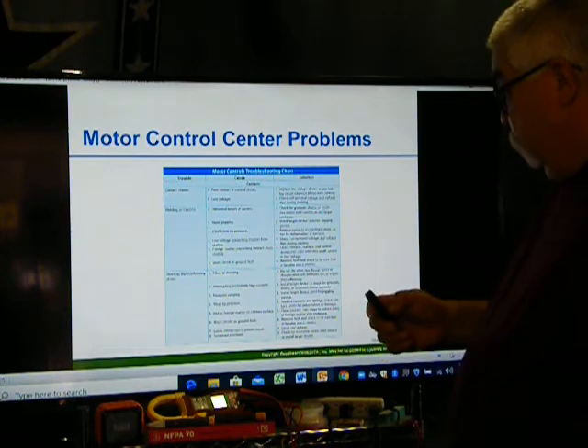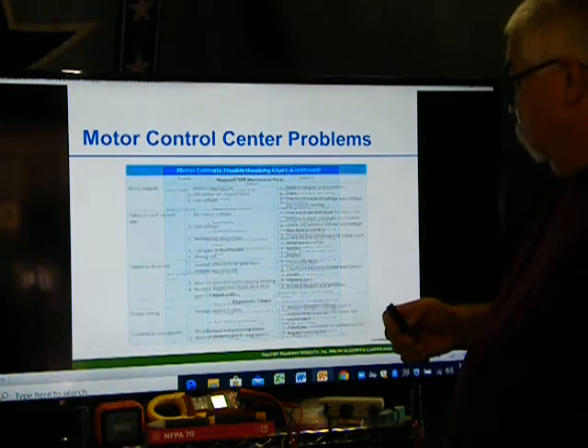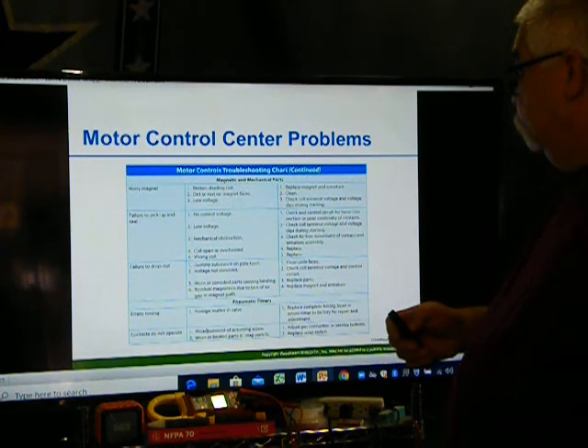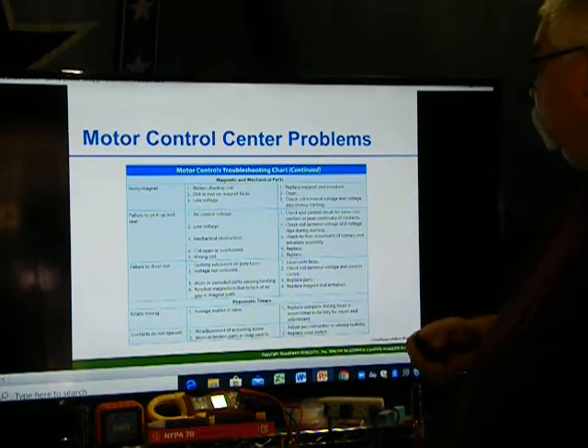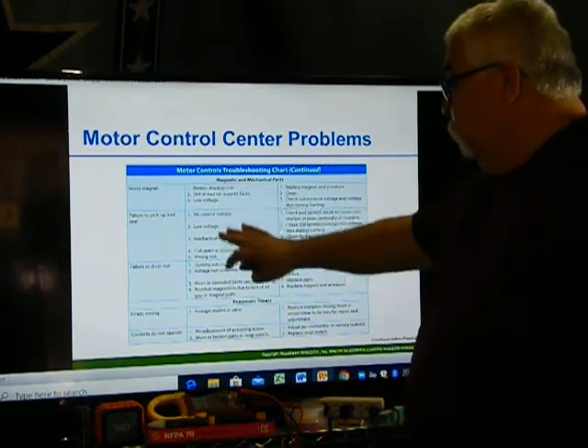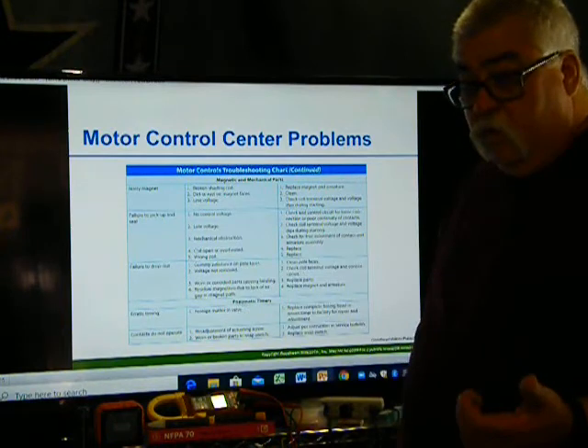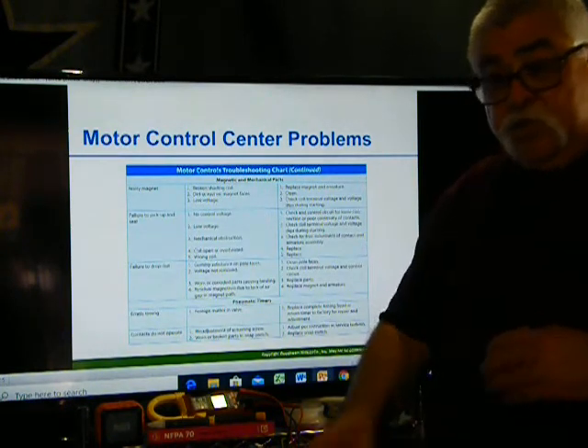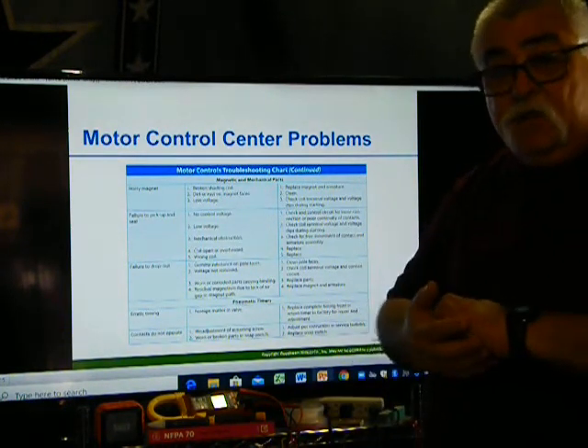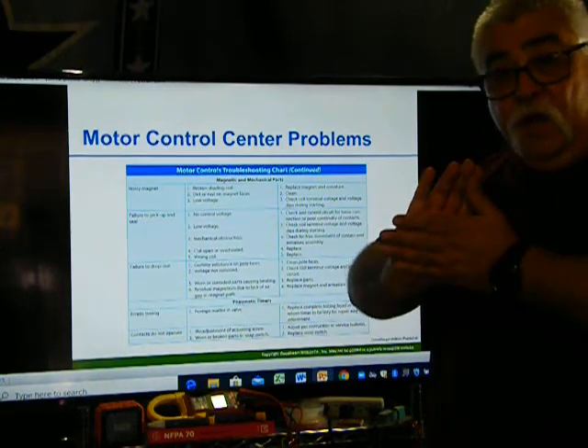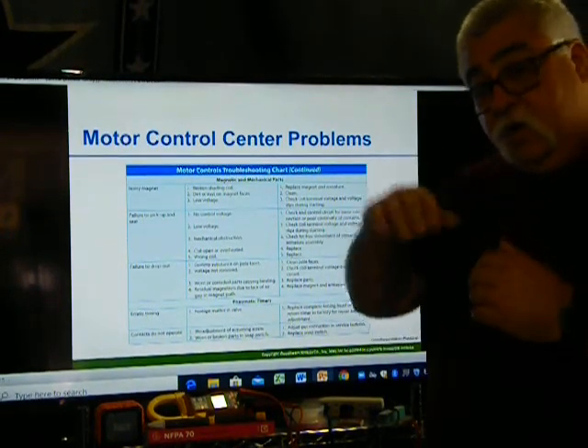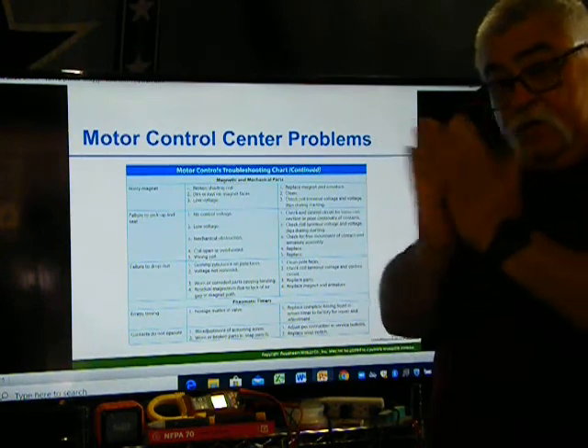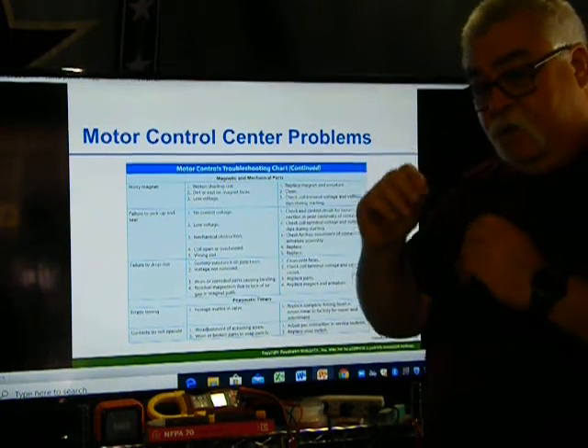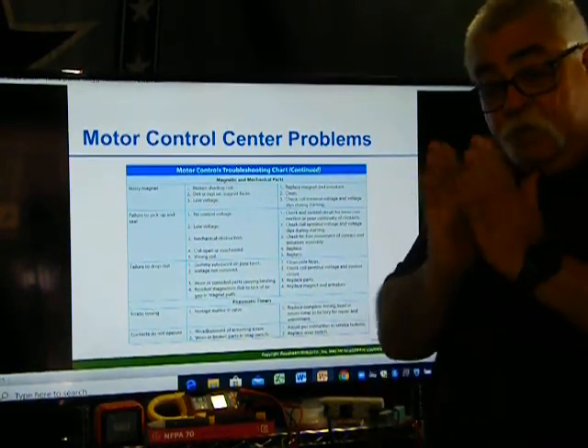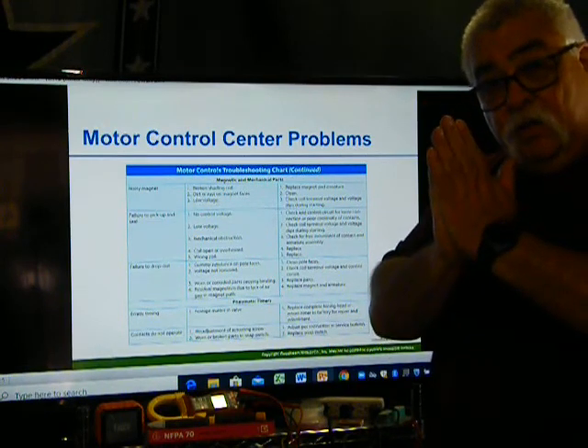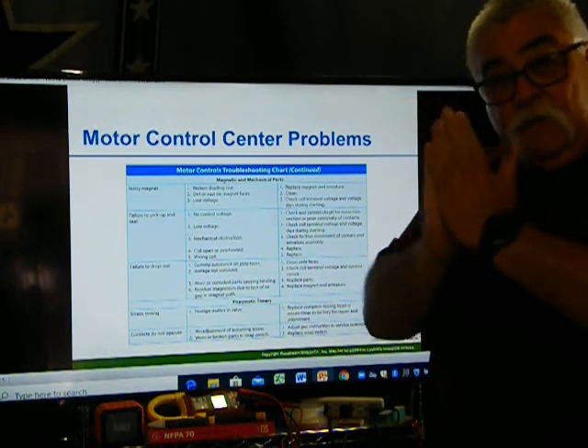So on the contacts, where is it? I'm trying to get to the one with the coil. Oh, here's the magnetic. But with these parts, the coil going bad, it doesn't close, or sits there and chatters. The contacts behind get dirty, so they don't make solid contact. Sometimes you got to go in there and clean the contacts off. Why? Every time it makes contact, it makes a spark, so you have debris that builds up. Sometimes that debris does not allow it to close, like you're clapping your hands.